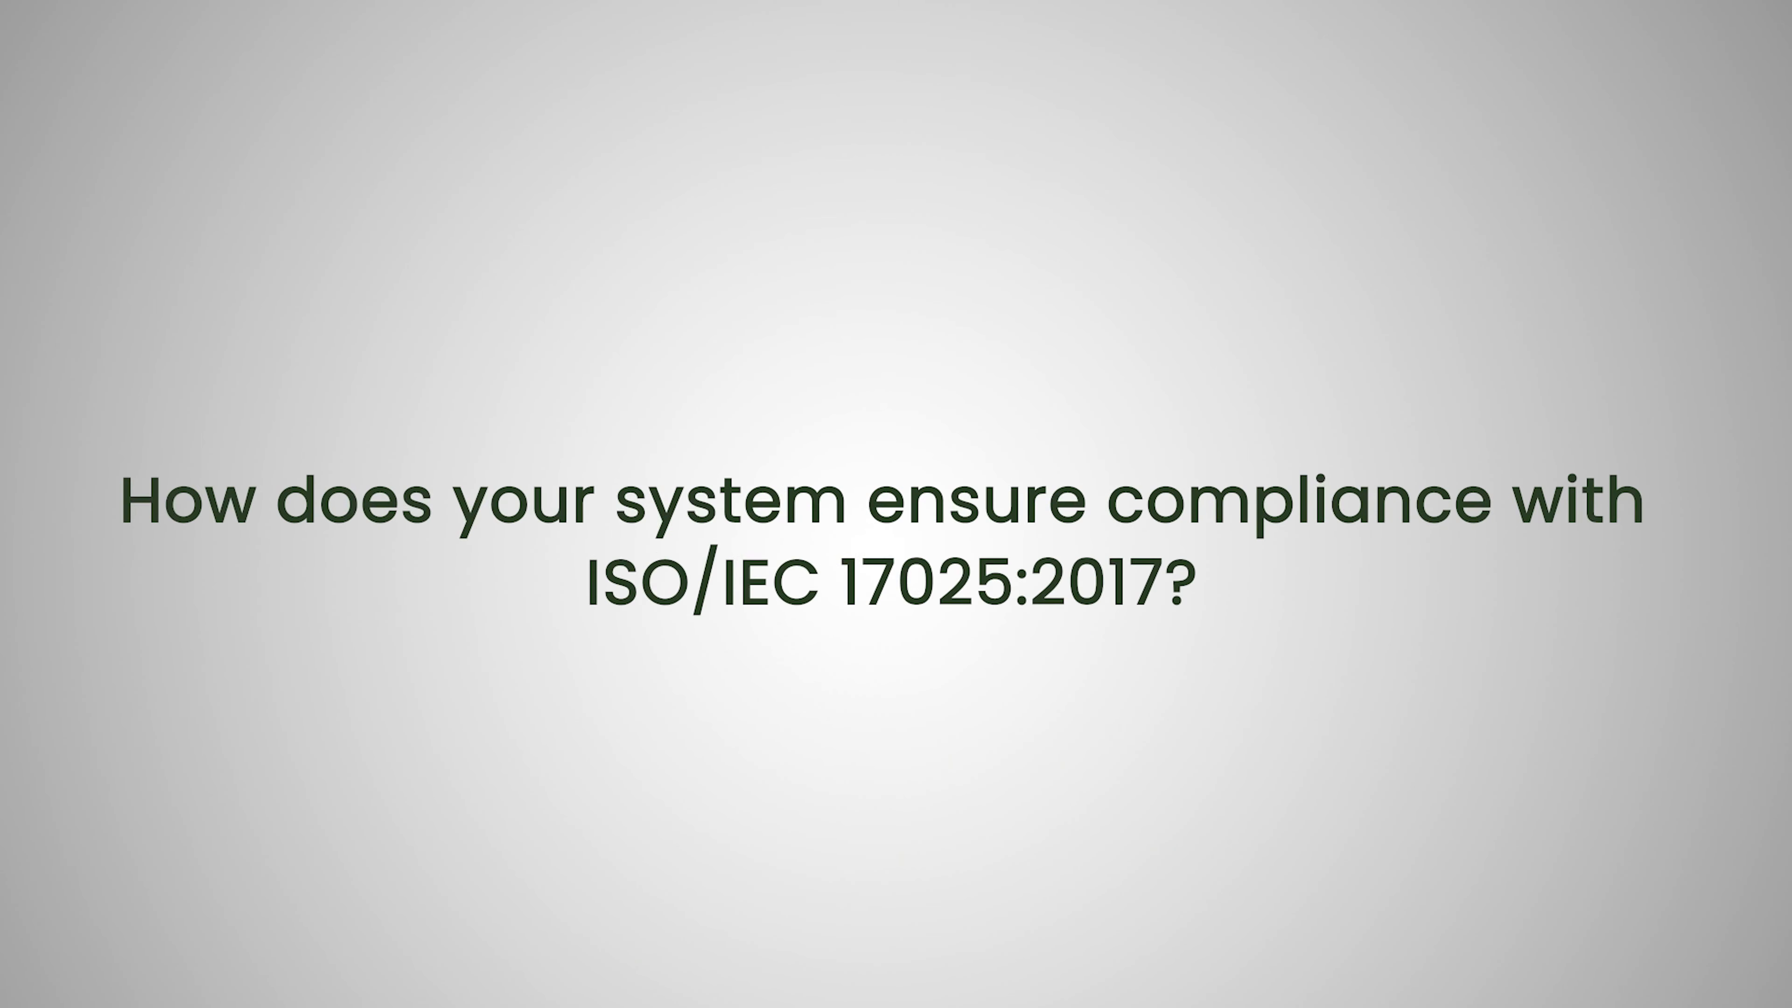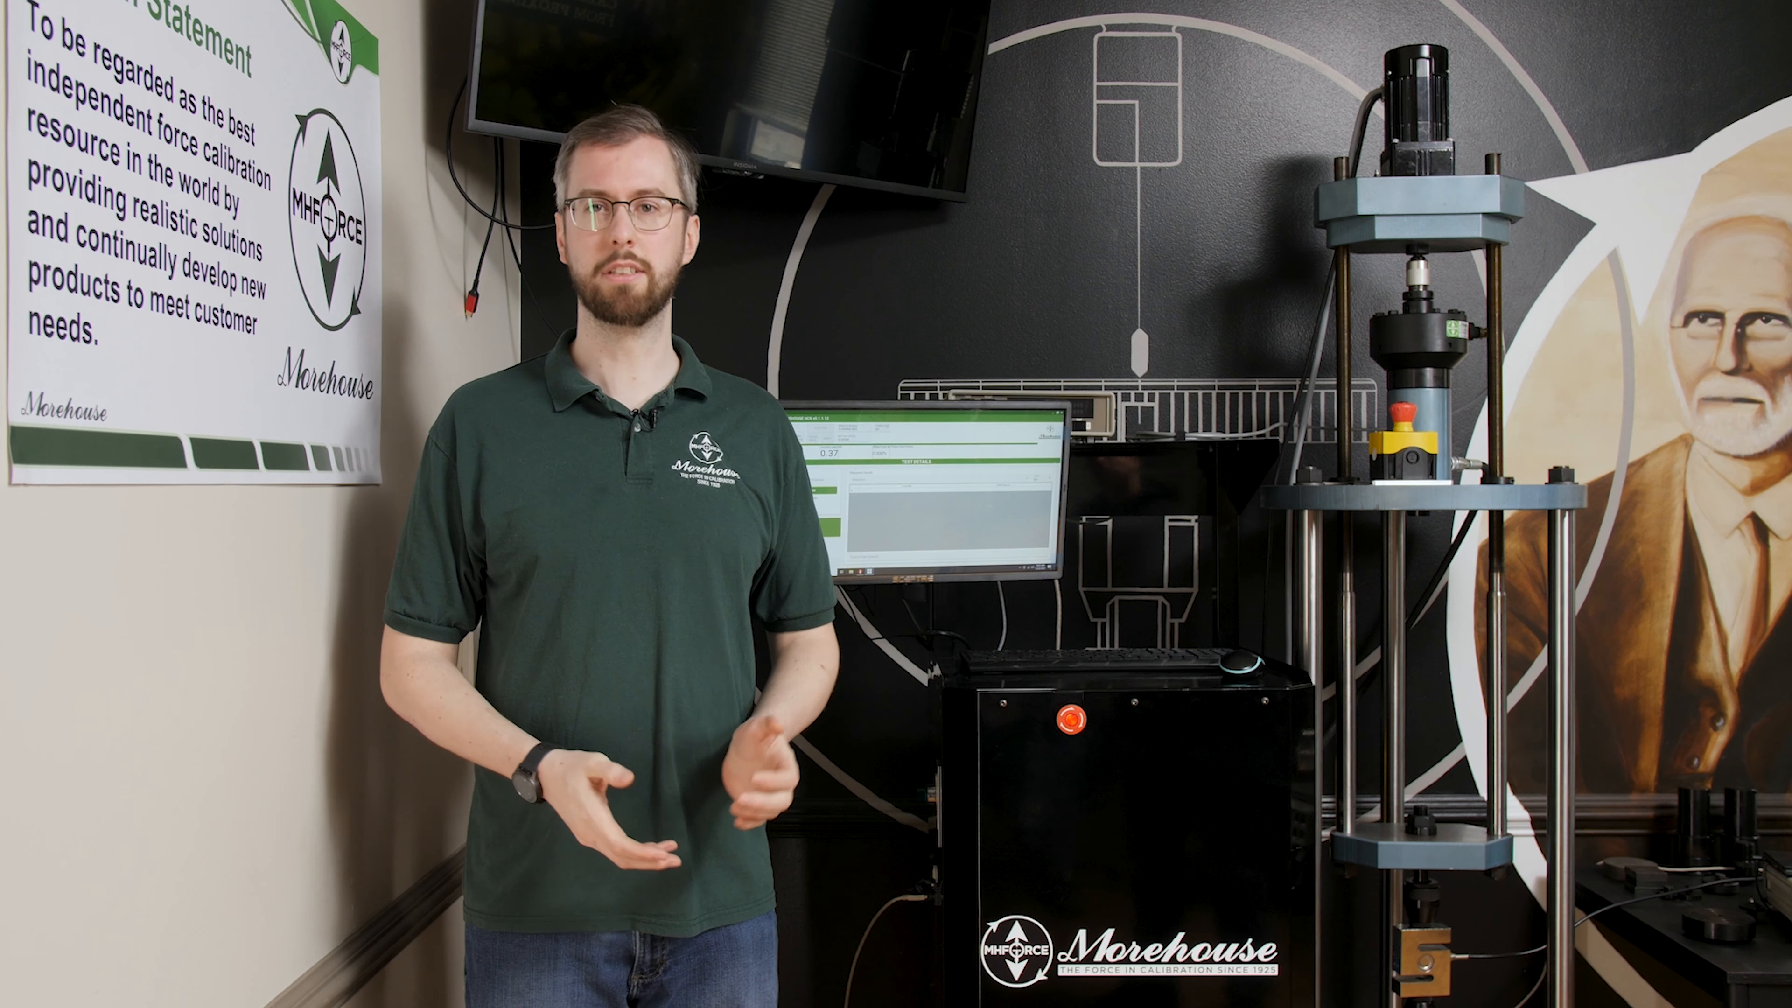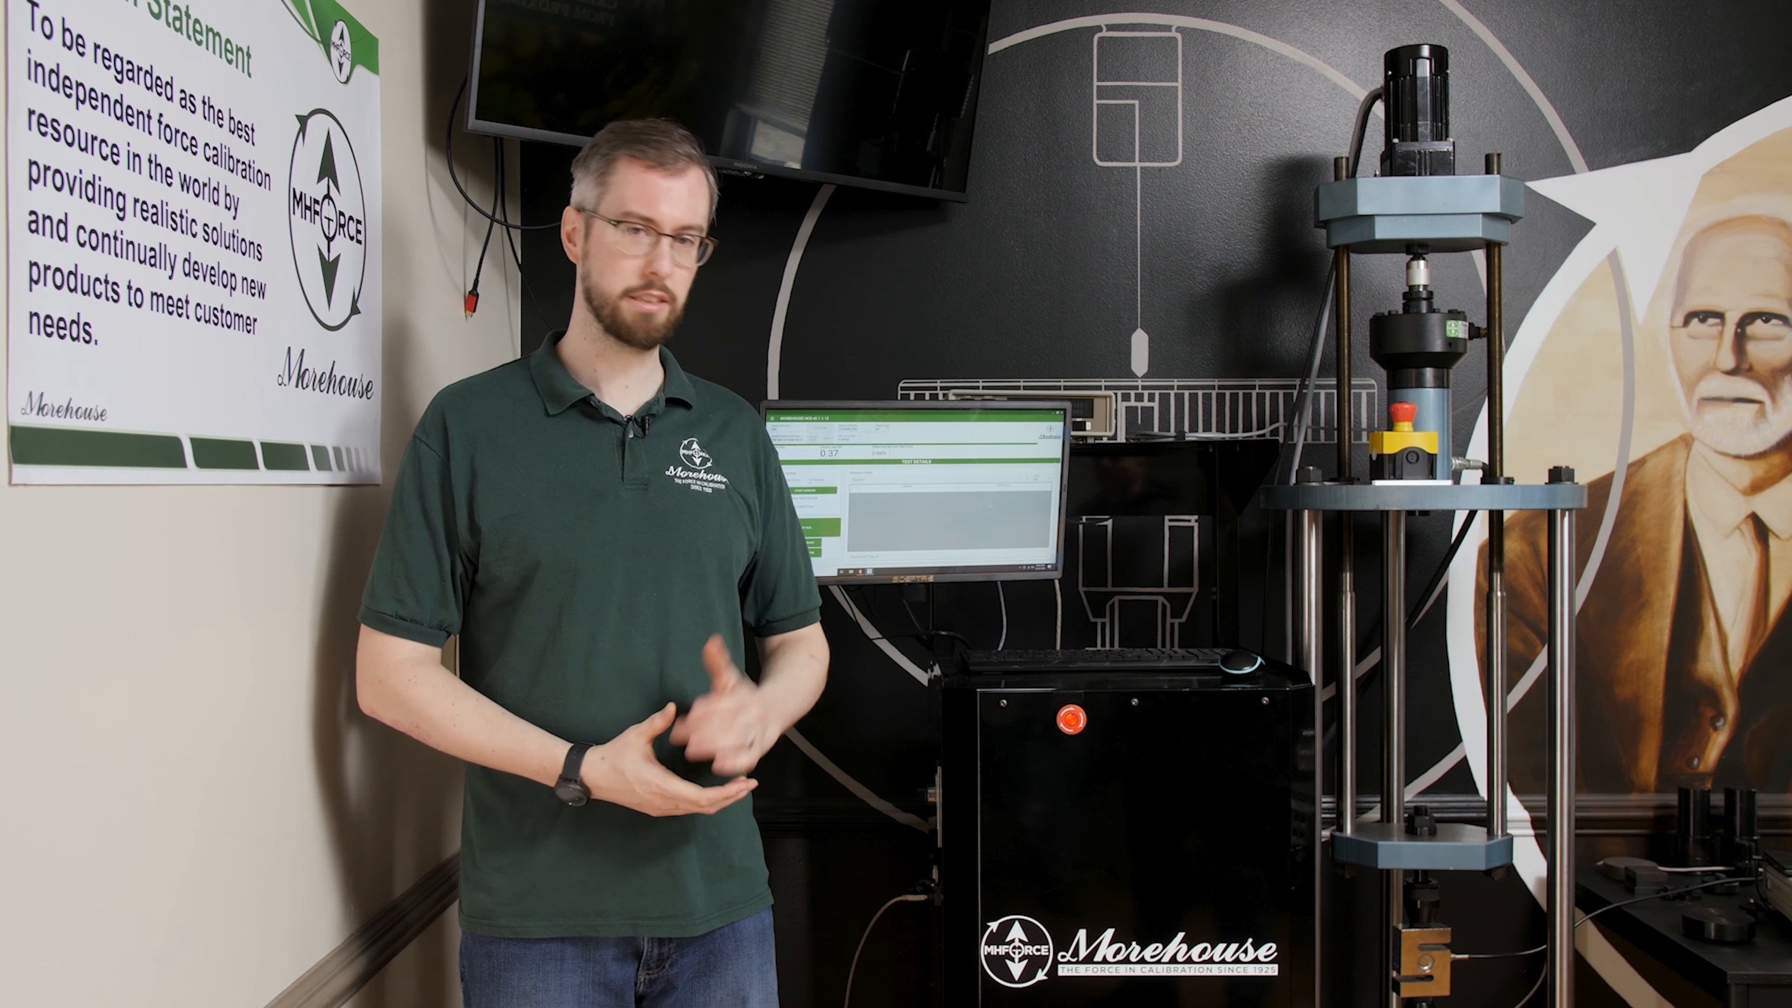How does your system ensure compliance with ISO 17025? 17025 has a requirement to keep all uncorrected data. So it's my understanding that a lot of systems do not keep that uncorrect, raw, uncorrected data, but our system does. It stores it in the calibration file for the instrument.